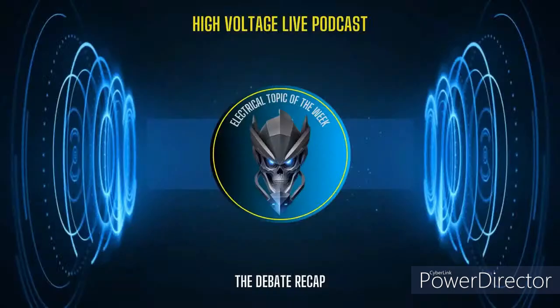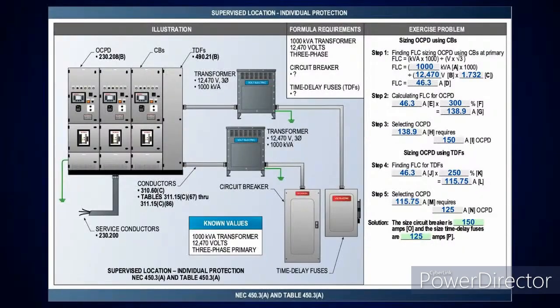Now, last week we were still doing sizing of overcurrent devices, and one of the things we were doing last week was the transformers. All right, now we're going to do the exercise problems here, and then after we get through this, we're going to start on motors. Okay, and I'm going to go through and explain all this. I've started at the start of every one of these on overcurrent protection devices. I've given a rule of thumb, and I've said if you take it at 125% or less, go up to the next standard size. Any percentage above that, you're going to drop down to the next standard size.